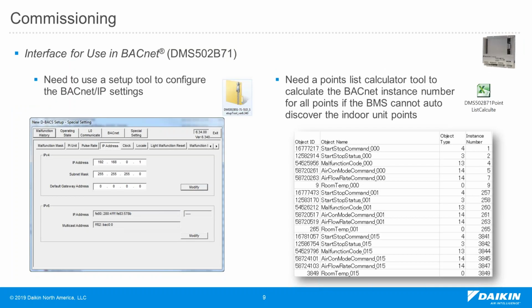For the commissioning of the hardware BACnet interface, we'll need a setup tool to configure the BACnet IP settings. That includes the IP address, the subnet mask, the default gateway address, and the BACnet instance number, and all the related settings, for example, BBMD. But it also needs a point list calculator tool to calculate those BACnet instance numbers if the BMS integrator cannot auto-discover the indoor unit points. So with this software tool, it can help calculate this list for each individual BACnet object. It will give you the instance number for the BMS to control.